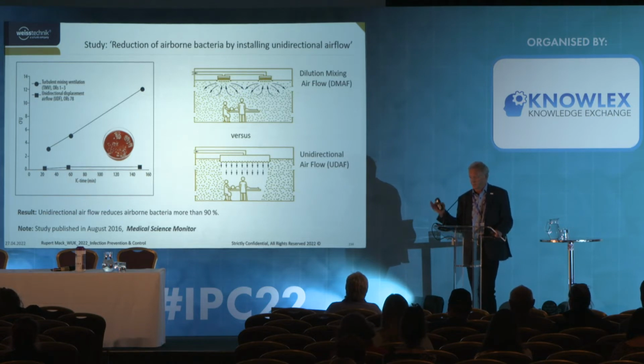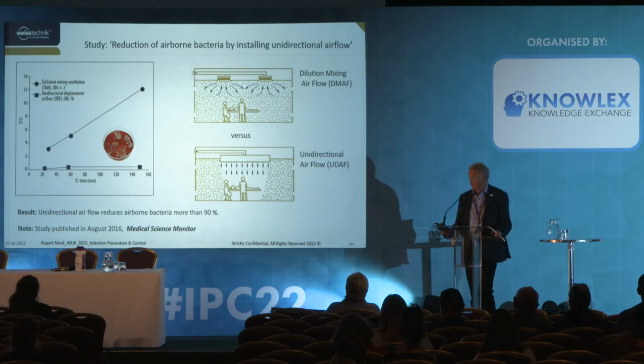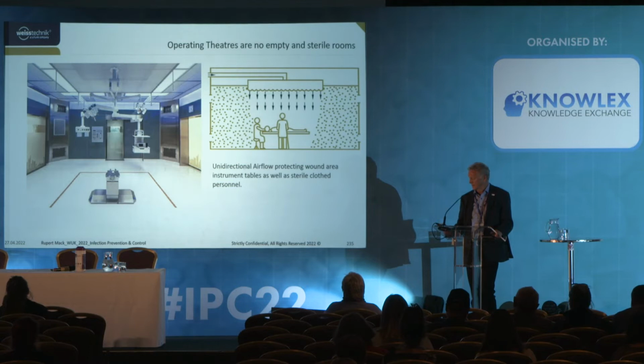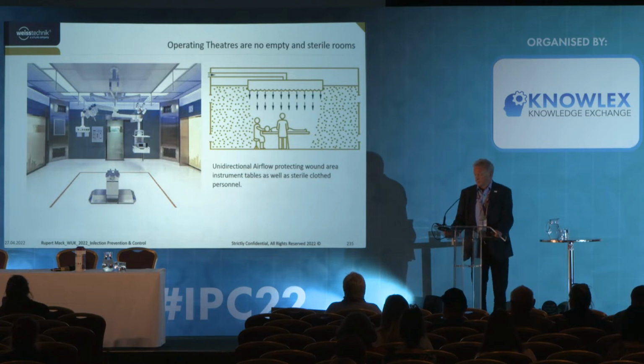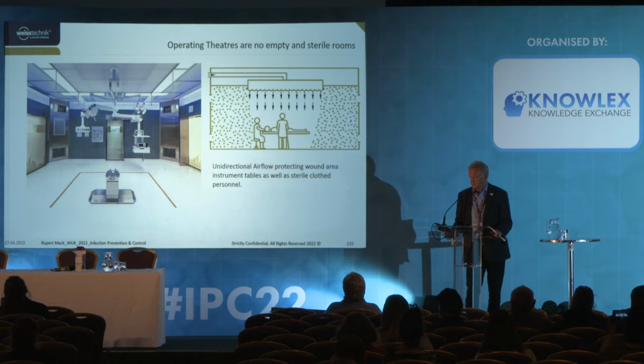So we can assume that the same result applies in terms of viruses, considering that if there are particles inside, viruses can sit on the particle, bacteria can sit on a particle, or nothing of them. But this study clearly shows that unidirectional airflow makes sense in order to have the best practice in infection prevention. So, as I said, an ultra-clean ventilation system has the task to make a protection zone that covers the wound area, instrument tables, as well as the sterile-clothed personnel.